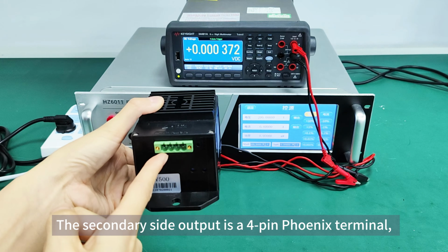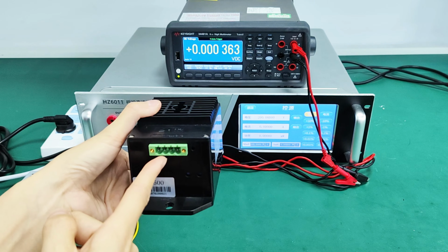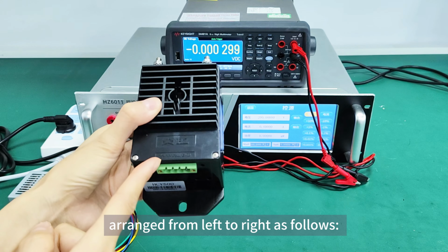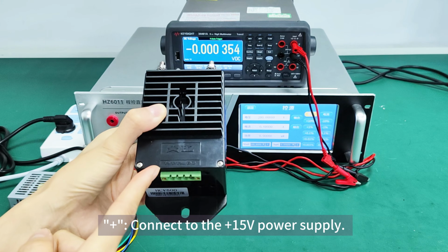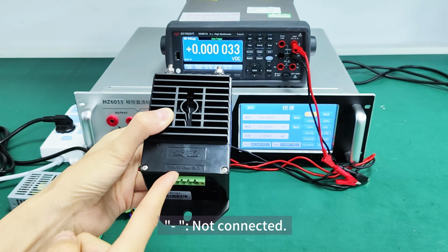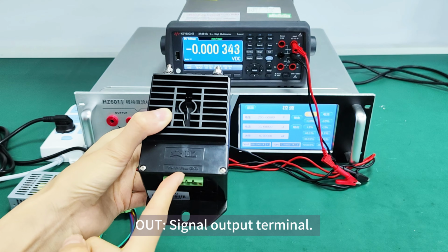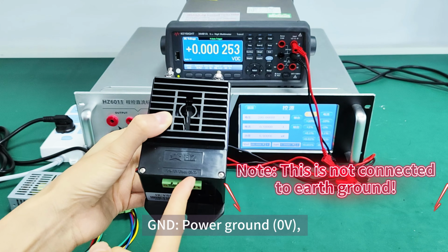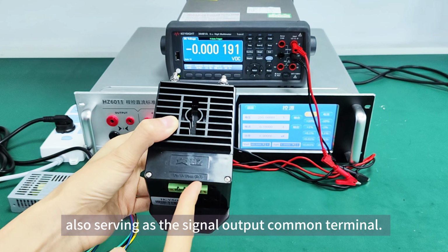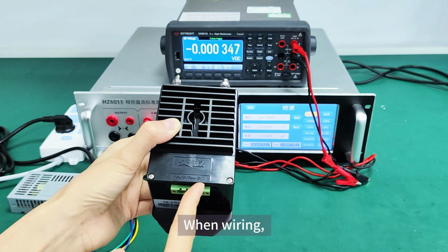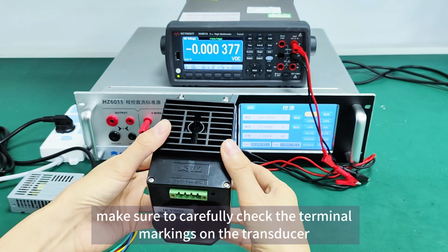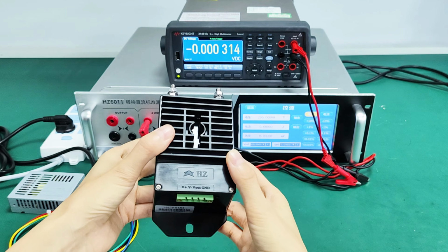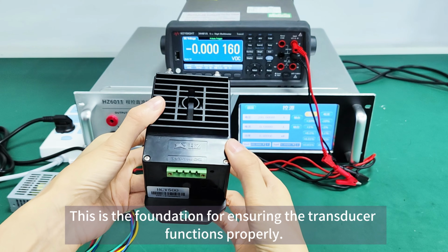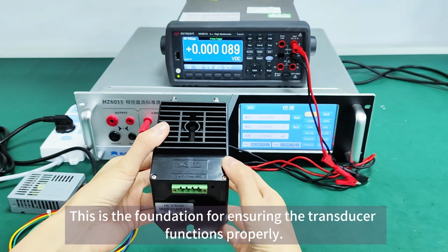The secondary side output is a 4-pin Phoenix terminal, arranged from left to right as follows. Plus, connect to the 15 volts power supply. Negative, not connected. Out, signal output terminal. GND, power ground, also serving as the signal output common terminal. When wiring, make sure to carefully check the terminal markings on the transducer to ensure correct connections. This is the foundation for ensuring the transducer functions properly.